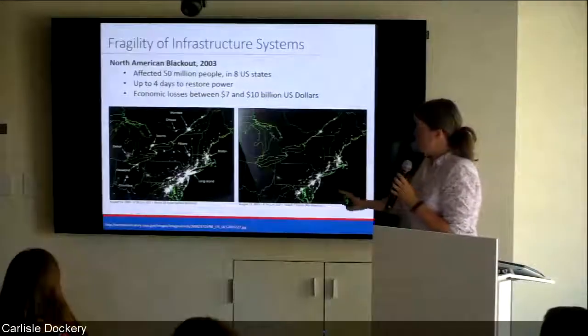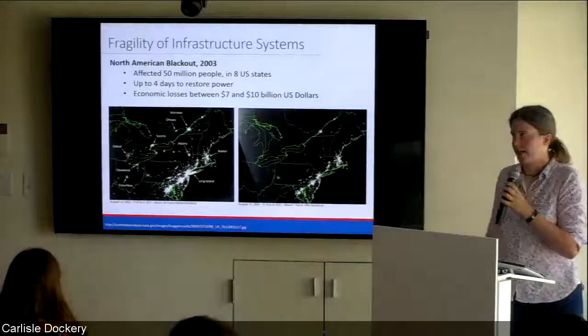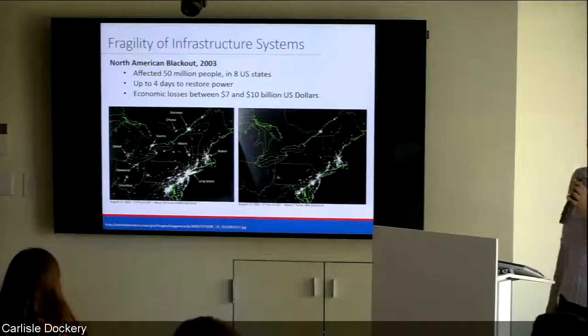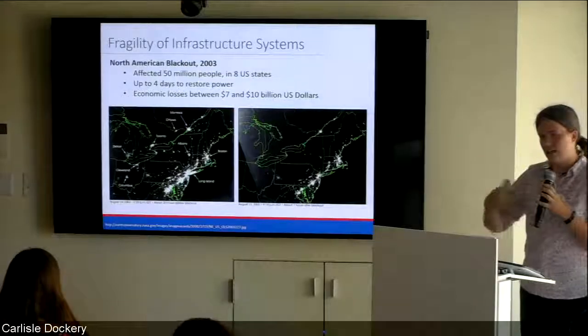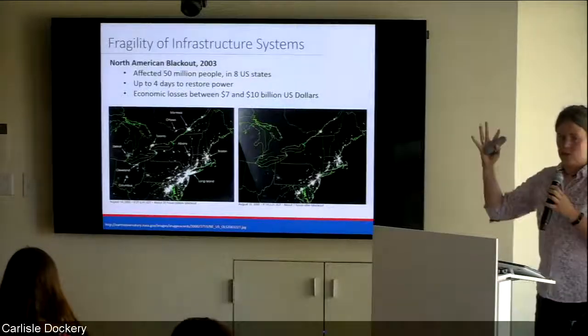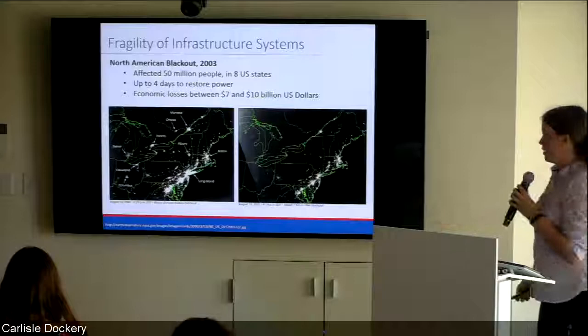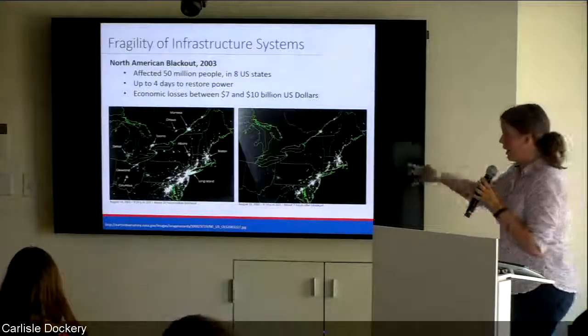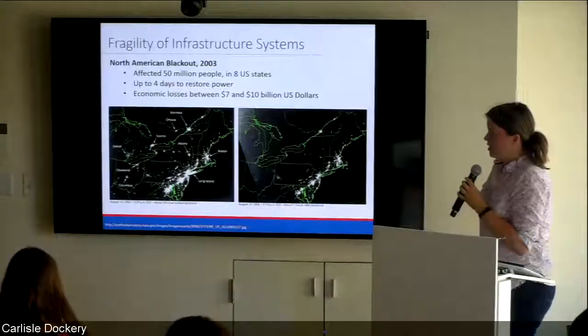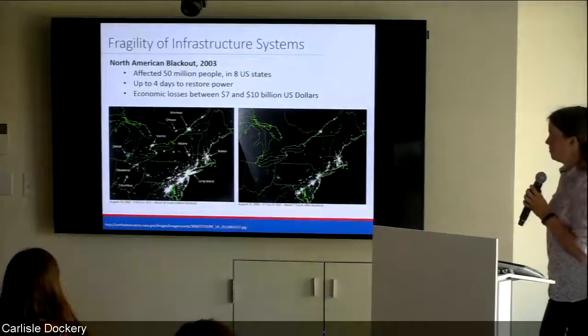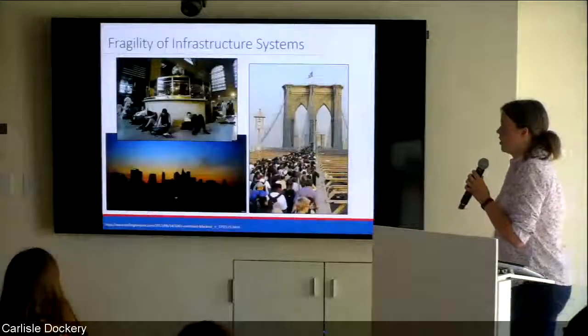It caused a cascading failure that started somewhere and then just blew up the whole system. Partly due to not managing tree growth around lines - lines when they get too much current on them start expanding and sagging, hit trees, and that cascades throughout the whole system. Once it starts, there's not much you can do; you just have to let it keep going until it eventually reaches stability, and then you can start repairing it. It's not just large-scale things that affect our infrastructure.